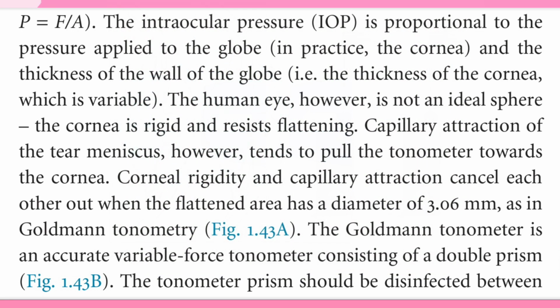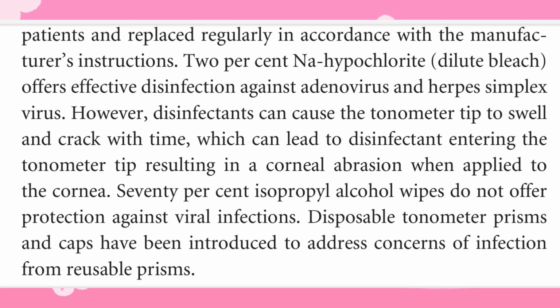The tonometer prism should be disinfected between patients and replaced regularly in accordance with the manufacturer's instructions. 2% sodium hypochlorite (dilute bleach) offers effective disinfection against adenovirus and herpes simplex virus. However, disinfectants can cause the tonometer tip to swell and crack with time, which can lead to disinfectant entering the tonometer tip, resulting in a corneal abrasion when applied to the cornea. 70% isopropyl alcohol wipes do not offer protection against viral infections. Disposable tonometer prisms and caps have been introduced to address concerns of infection from reusable prisms.